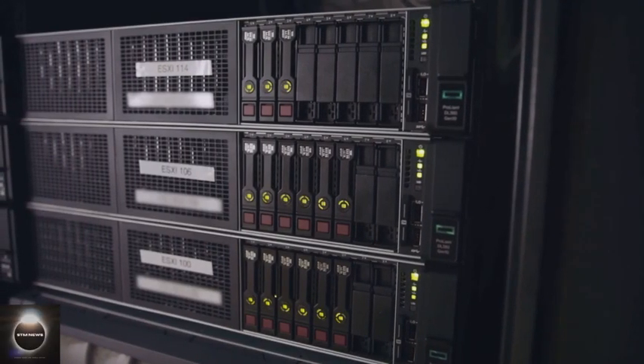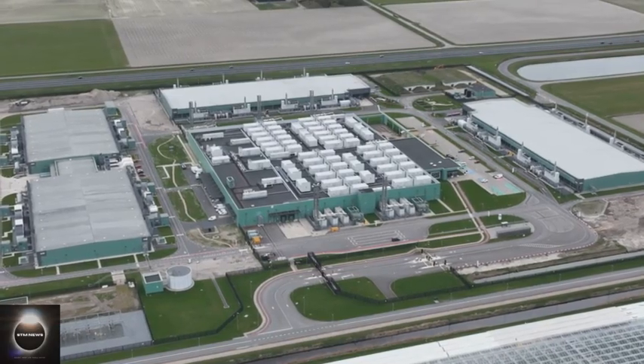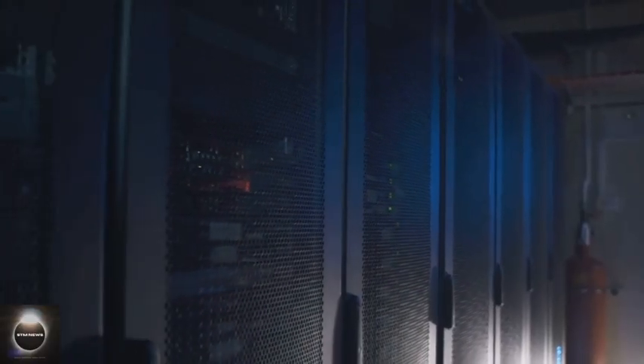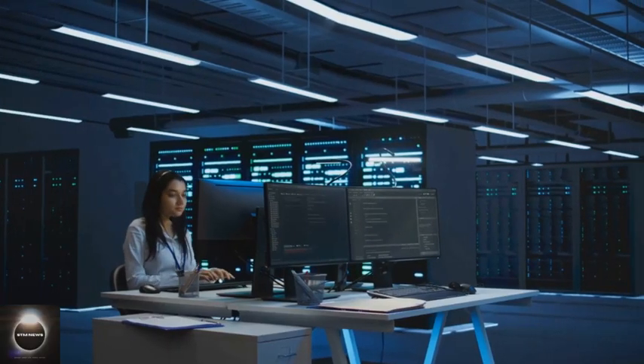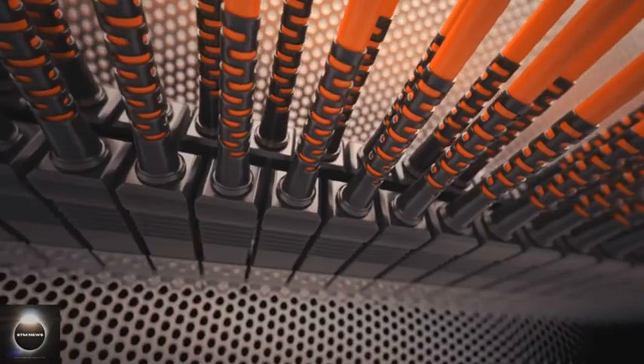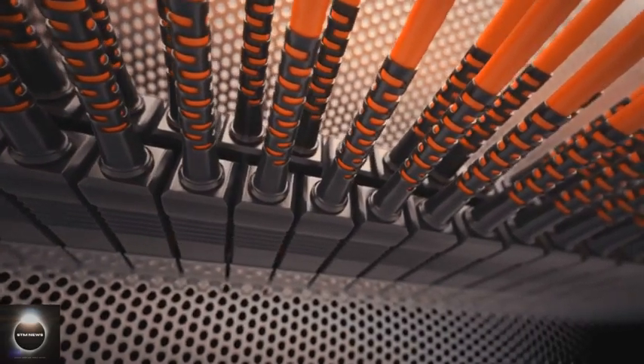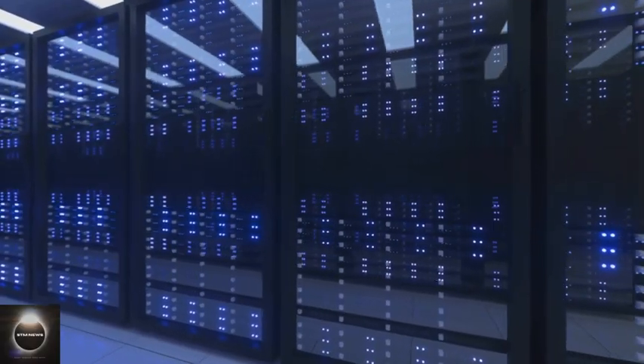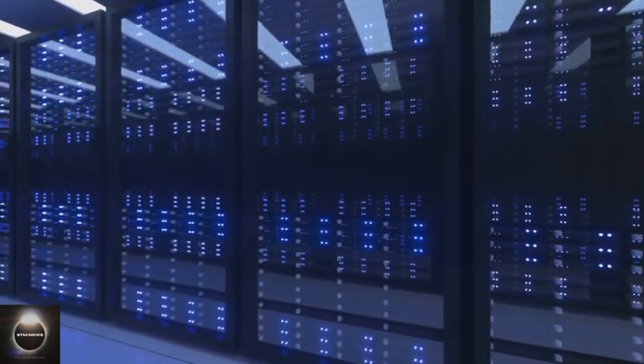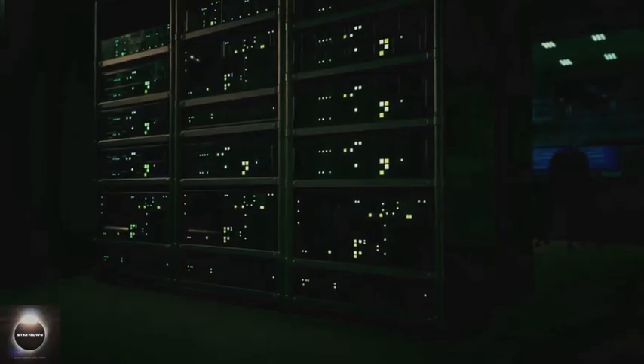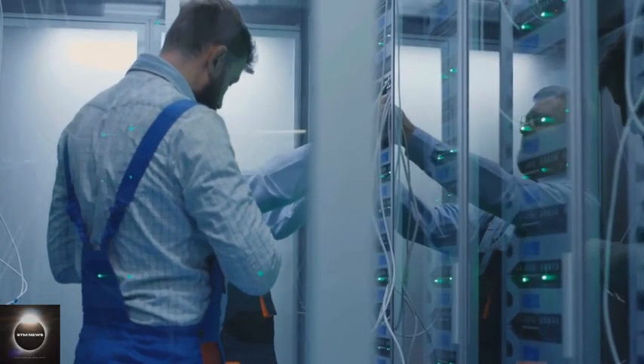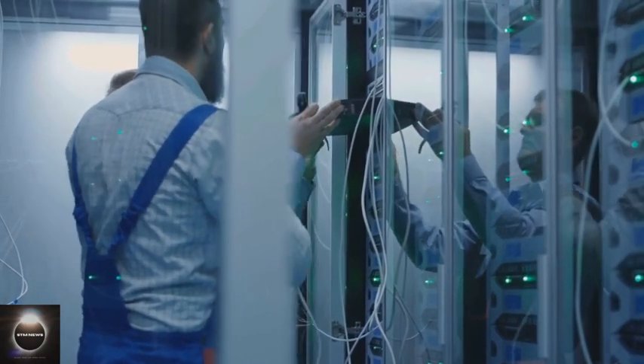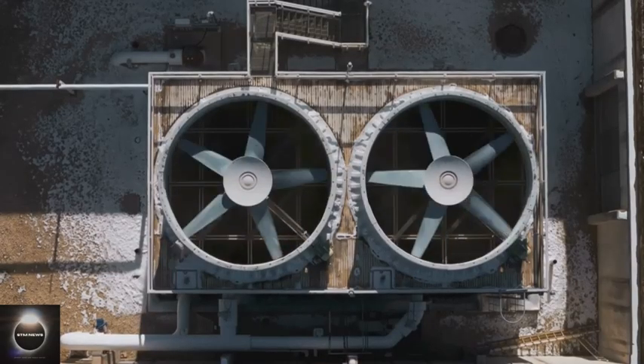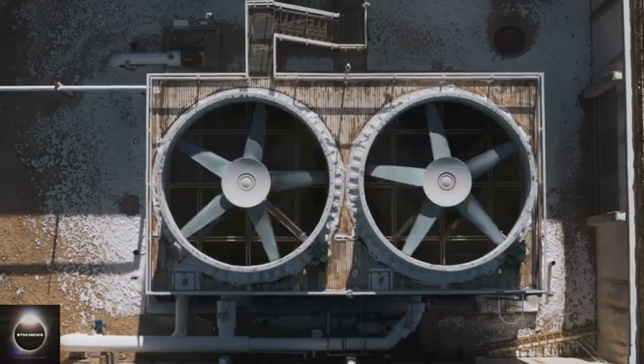Continuous operations create two fundamental challenges: power and heat. First, deliver stable electrical power. Second, remove the immense heat servers generate. These systems are intertwined and define data center engineering. If power falters, the digital world goes dark. If cooling fails, servers overheat and shut down in minutes. So from the largest generator to the smallest fan, every component serves reliability. Even brief downtime has real consequences. For construction, electrical, and HVAC pros, every system here is critical. Facilities can rival a small city in power use, with cooling plants to match.